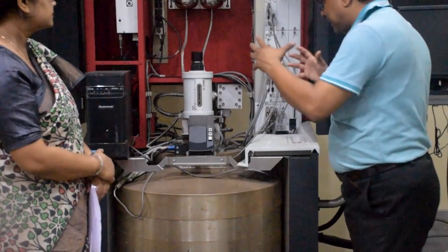During the lockdown, the basic system was supposed to be maintained at 2 Kelvin throughout the year, but since there were power failures and we were not able to attend to the instrument regularly, the whole system evaporated, particularly during Amphan, when there were power failures for several days. After that we have been unable to bring it back into working condition, but at any moment we can, provided we use the liquid helium gas. It has the fantastic facility of converting this gas so that it can be used.